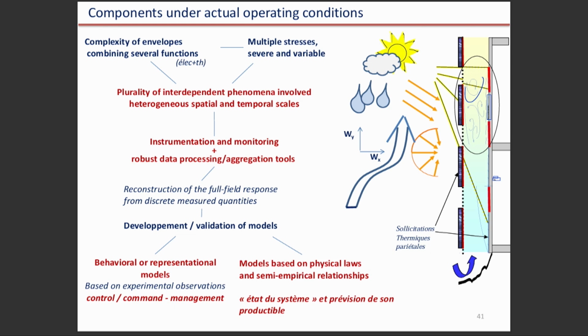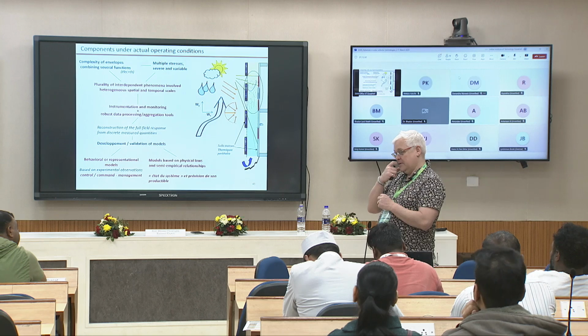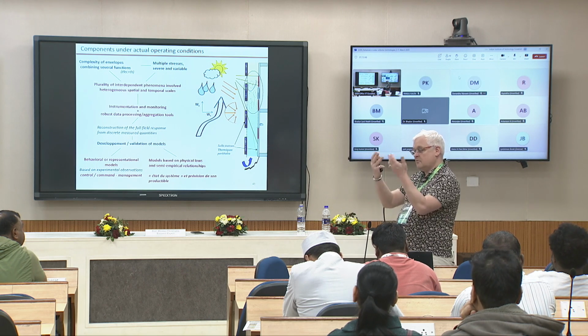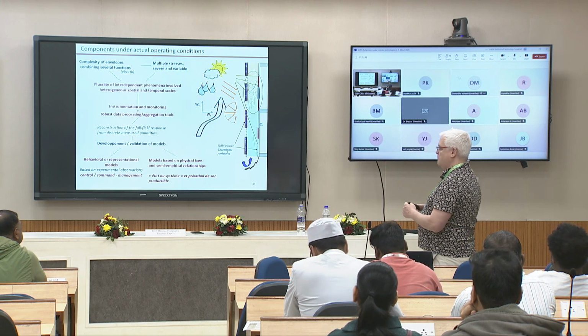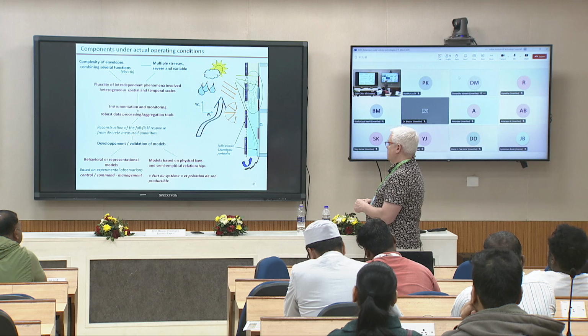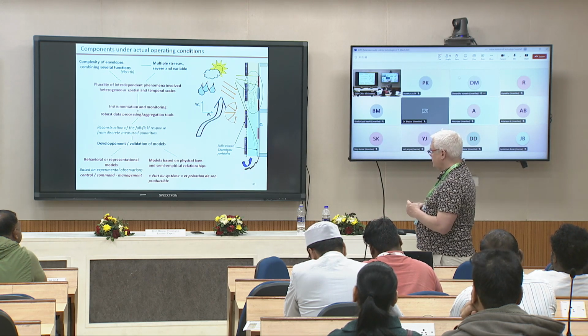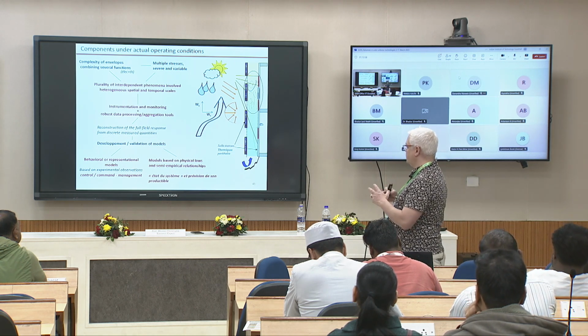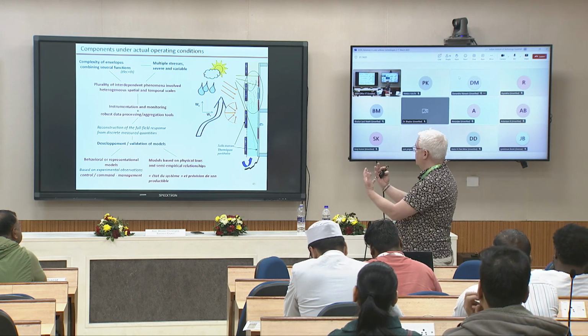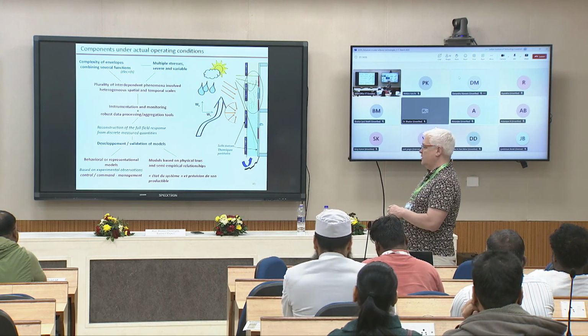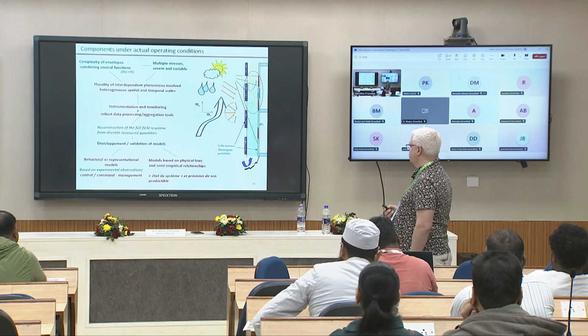Those are the only two natural engines of ventilation: difference of pressure or difference of temperature. And if there is a fight between the difference of pressure and the difference of temperature, it is the wind that will win. The wind is much stronger than the air movement induced by difference of density. So it's complex to design, and also to find solutions in order to be sure that there is a good enhancement and heat transfer in such a configuration.